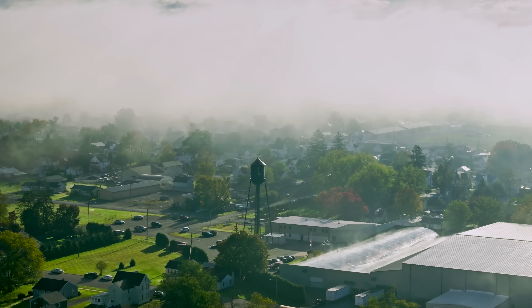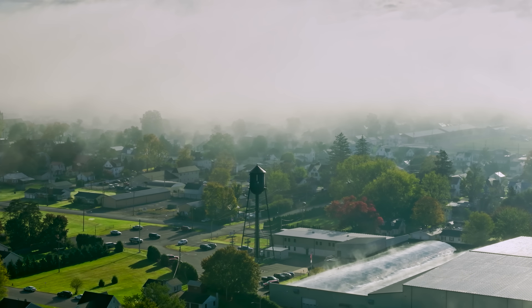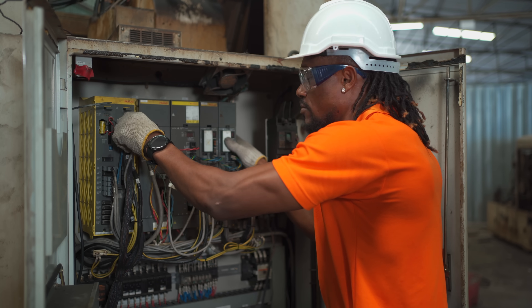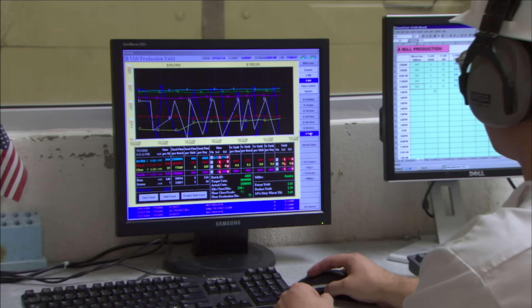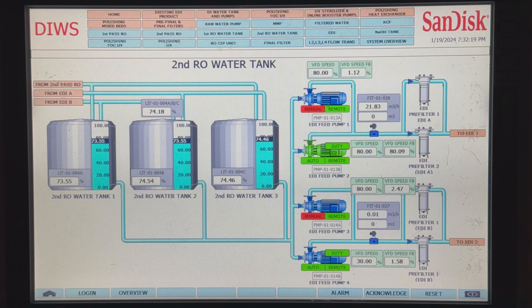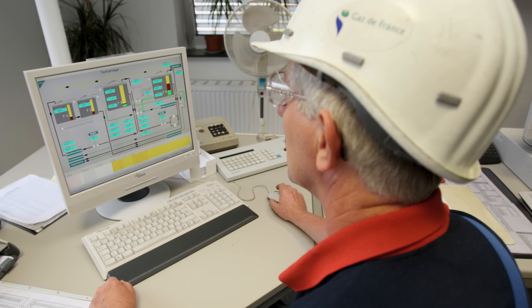You don't have to manually control the pumps or be on site to check the tank level, and you can change those setpoints. Maybe during seasons when demand is low, you don't want the tank full all the time because the water spends too much time in there and its quality can degrade. Any trained operator can just change the values in the HMI. They're designed for simplicity — I've always thought they look a lot like old video games, with something really nostalgic about their basic graphics. It's easy to forget that they're connected to real, often large and complex systems where the stakes are high — which is exactly what happened in Muleshoe.